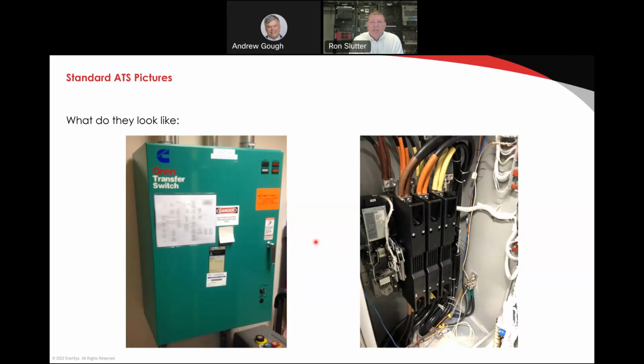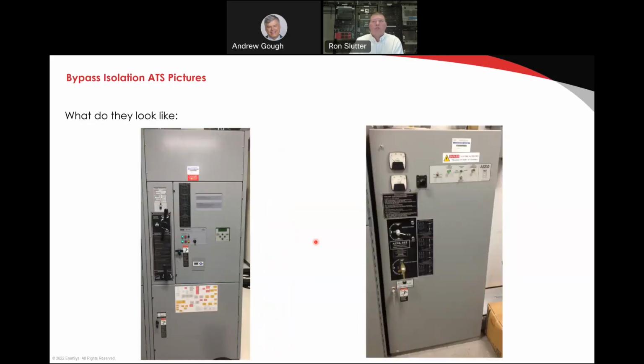I've been in facilities where they store their keys inside of this box, where they store any number of things. Sometimes they put a hub in there that you guys need to get into. I would caution you against that. It is a very dangerous activity to open the box and have exposed live bus unless you're a qualified electrician. All right, so that's what a standard switch looks like. This again is 3-pole. They do come in 3-pole and 4-pole switches, and I'll explain that later.